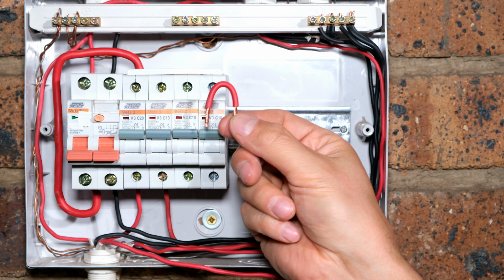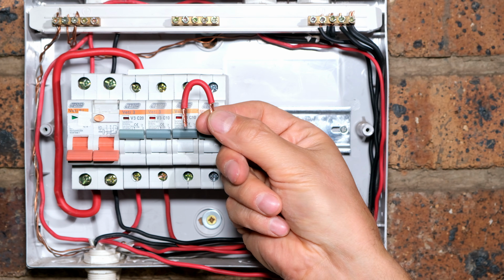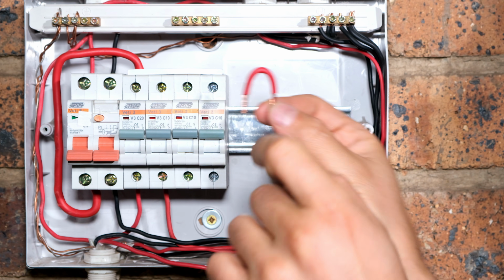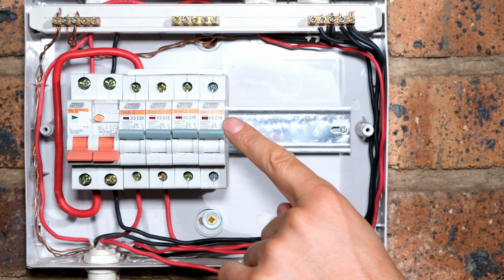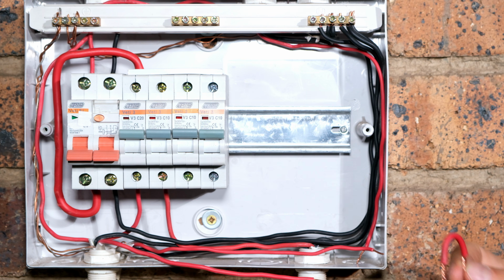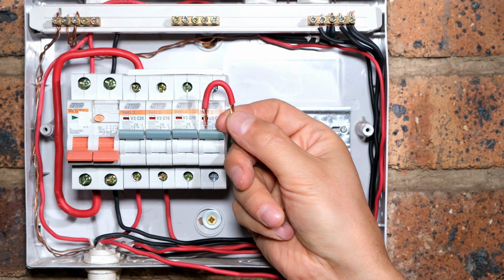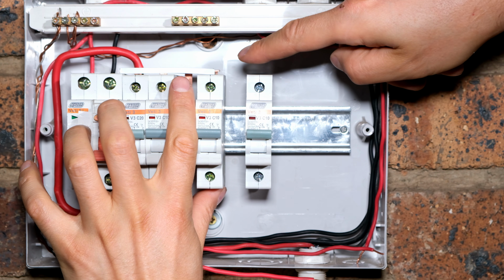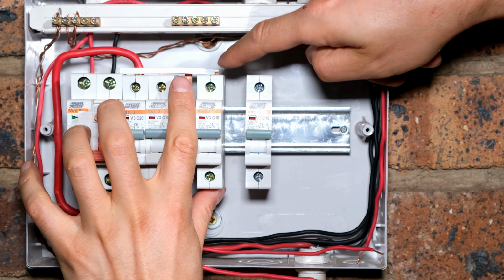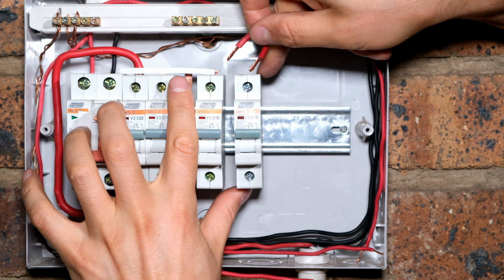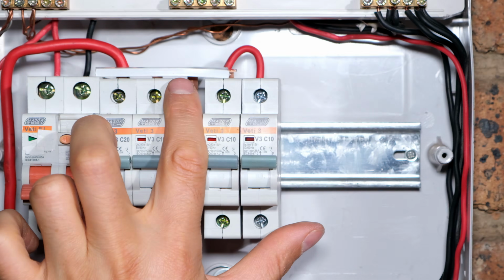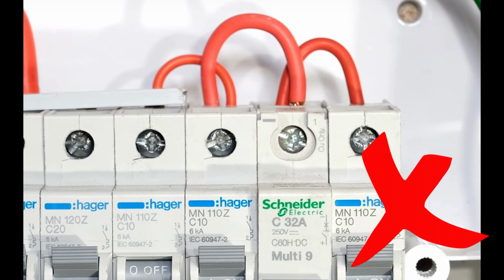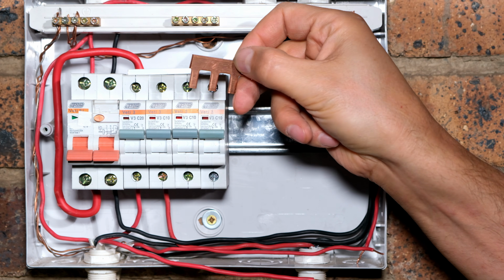Now, yes, some people will just use a jumper. If you are going to use a jumper, make sure the wire thickness can handle the rating of the circuit breaker. So this is a 10 amp circuit breaker, and this wire here can handle 20 amps. If, for example, the board was quite full and the bus bar was already at its maximum, then yes, you could add a jumper like this. And never add a jumper to another jumper. Although for best practices, please use a bus bar.